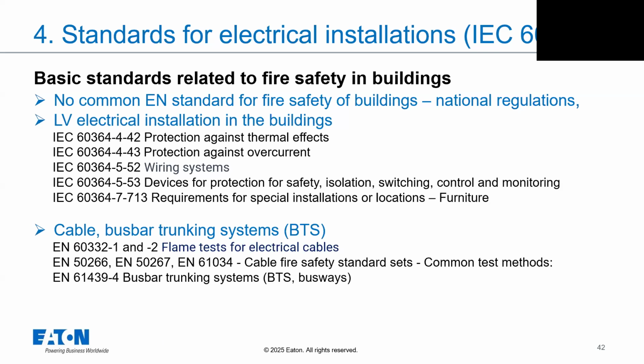Separately, if we need to design a new installation, we must be careful about the selection of cables. Here the basic standards for flame tests for electrical cables are mentioned, also for busbar trunking systems. Generally, if you are in a situation where you must design an installation with higher fire resistance and so on, the general approach is to use as much busbar trunking system as possible. Why? Because a busbar trunking system contains less plastic material, which creates gases and is flammable, in comparison to cables. This is the first moment when you have the possibility to use a busbar trunking system from a fire protection perspective. Definitely a busbar trunking system is preferable.